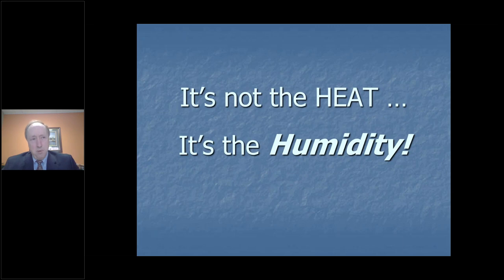Okay, if you have a plate type heat exchanger or even a wheel type heat exchanger, where you have a contaminated air source coming from the building because of some type of exhaust or relief air, if there is a concern, maybe tuberculosis or COVID or whatever the contaminant is, that it would be brought back into the building, yes, do not use any type of wheel or plate heat exchanger that has the air paths across. Now, oftentimes in a plate heat exchanger, the plates are separating the incoming ventilation air and the exhaust or relief air, so you might be okay with that. But yes, you never want to mix the air streams. So you would certainly make sure that whatever technology you are using is not going to let the two air streams touch.